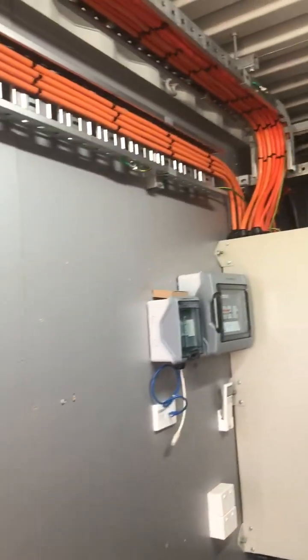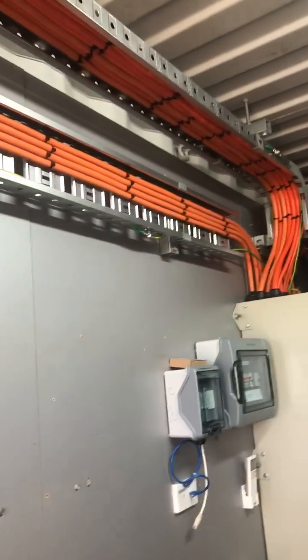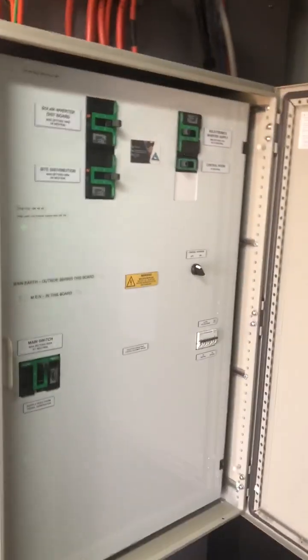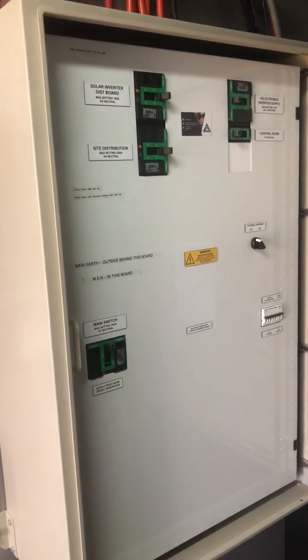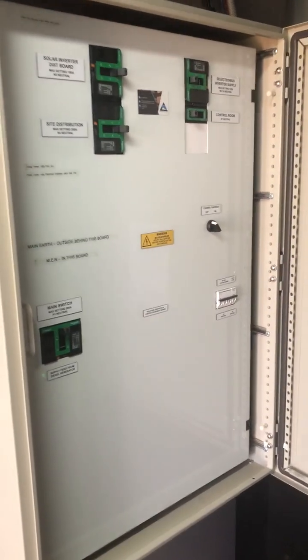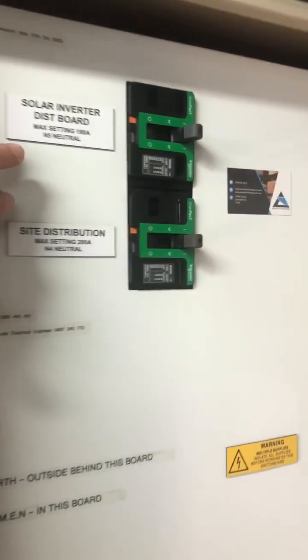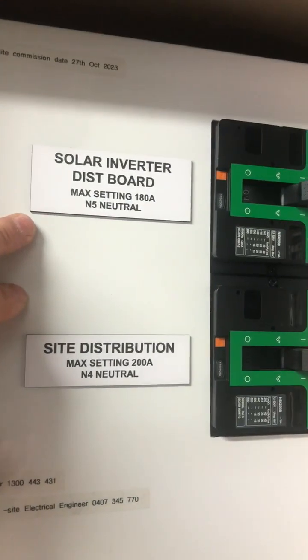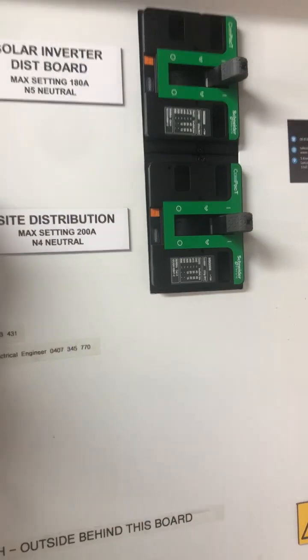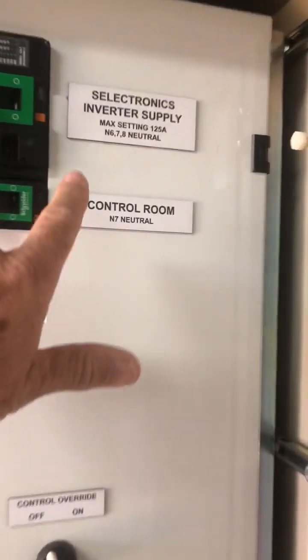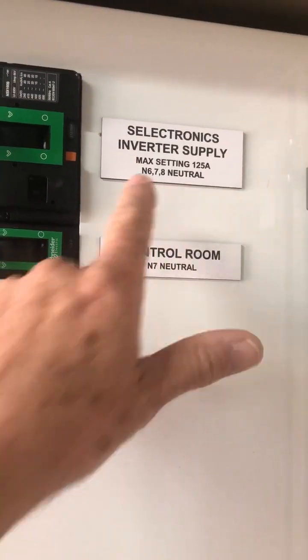Then we'll go to the main board. As I said, all the energy at the moment is flowing from the PVDB and coming over into the main distribution board, which is here. We designed this board and had it made by a manufacturer. It's a specially made distribution board, and you'll notice that up the top here we've got the solar inverter distribution board. This goes out to the site, and we've got the inverter, the Selectronics inverters.